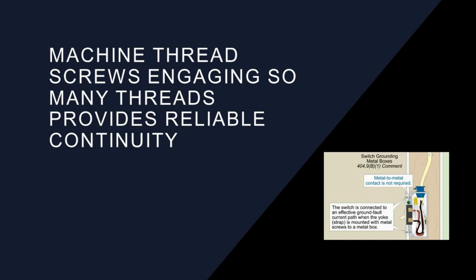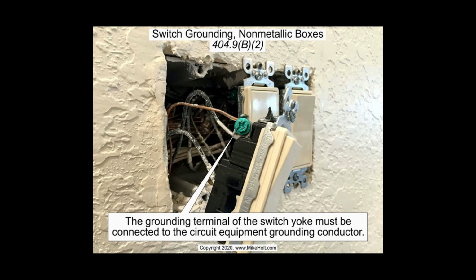All right, machine thread screws engaging so many threads provide reliable continuity. So this is what I was talking about. Those 10-24 threaded screws on the industrial covers are too far apart, and they do not have two threads inside the metal, and that's why they have to have that ground. Switch grounding, metal boxes: the switch is connected to an effective ground fault current path when the yoke is mounted with the metal screws to a metal box. So if you put a drywall screw in there, it doesn't count. You definitely need a yoke if you did a drywall screw. And if you did a drywall screw, technically you should probably fail it for not using the correct screw with the correct device, but just food for thought.